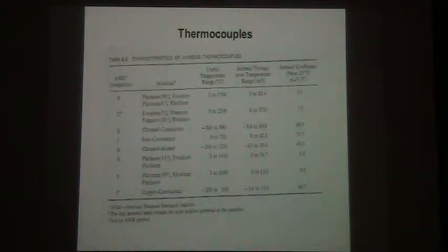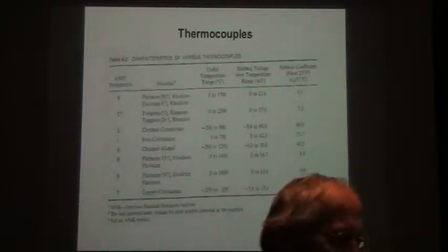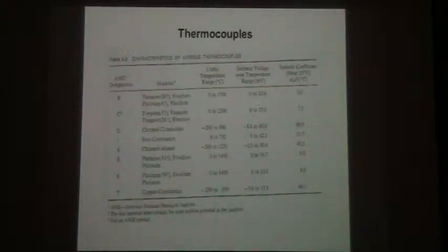No. It worked. Okay. We have different combinations of thermocouples. We are obtaining different temperature ranges and different sensitivity. The Seebeck coefficients are listed here. Now, even if the output signal is so low, when we are measuring high temperatures above 2000 degrees centigrade, the output signal will be substantial. Yeah? Because if it is, let's say, 80 microvolts per degree centigrade, for 2000 degrees centigrade it will be pretty high.